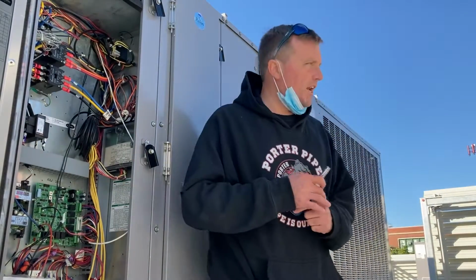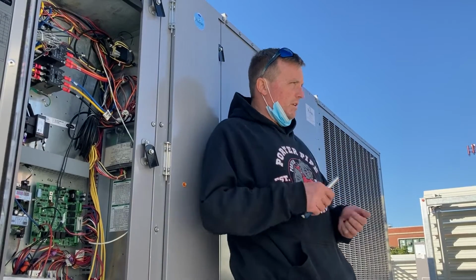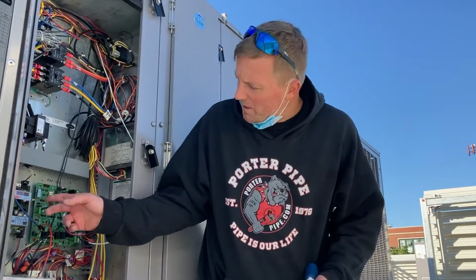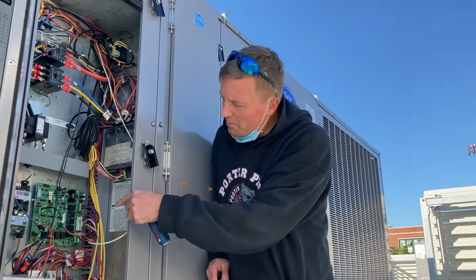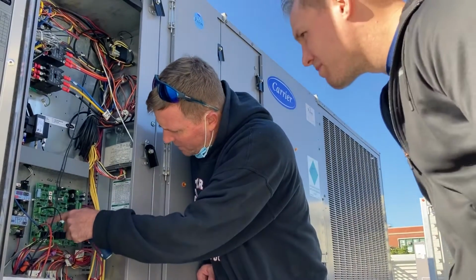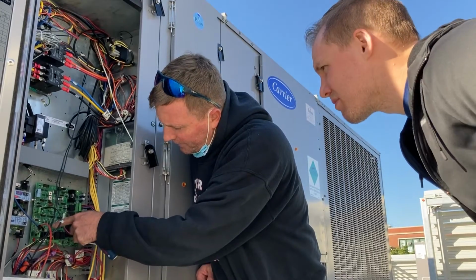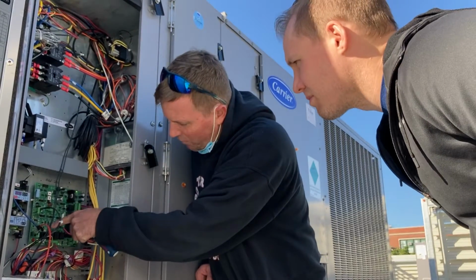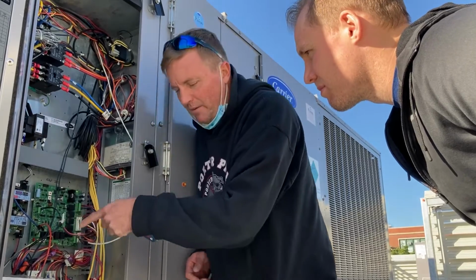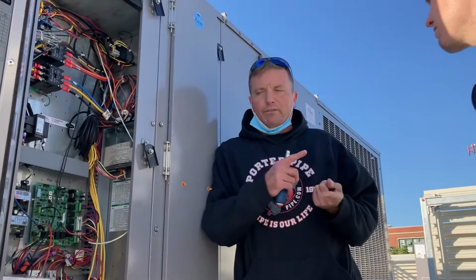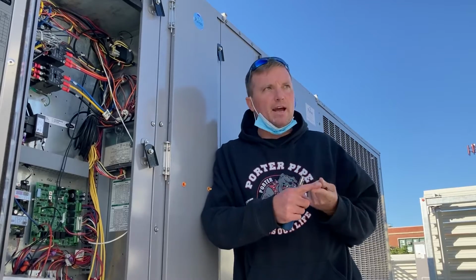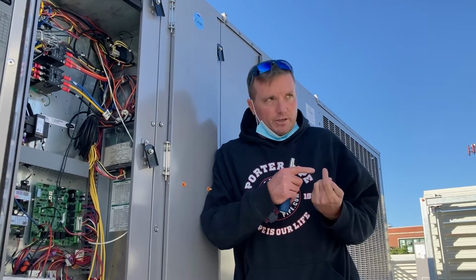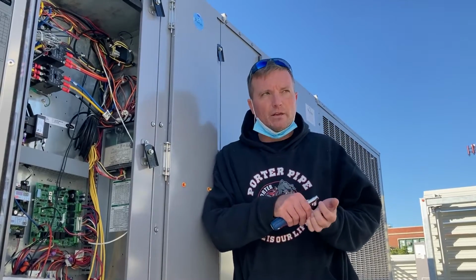So if we lose any kind of communication, as far as when you get this up and running, we always want to make sure that on the board here, if you want to come over, that we don't have any red lights down here. See, there's an error light. It says run blinking green, and next to it is an error light. If it's an error light, it'll show an alarm, or if there's any point that they've pulled on the BAS, high pressure, low pressure, whatever kind of trip there is, it will come up as either a general alarm, or if they have a sensor hooked up to the BAS, it'll tell you exactly what the problem is, okay?